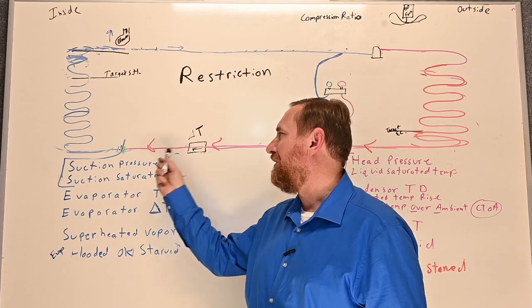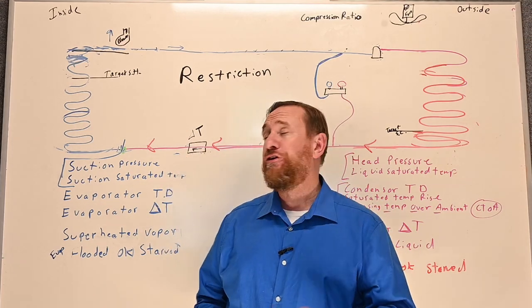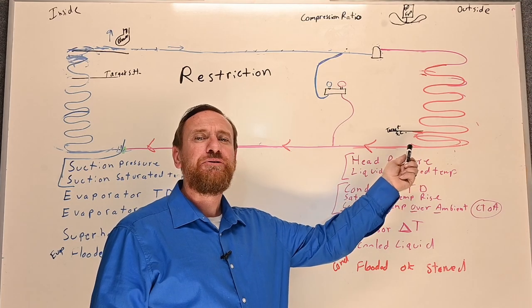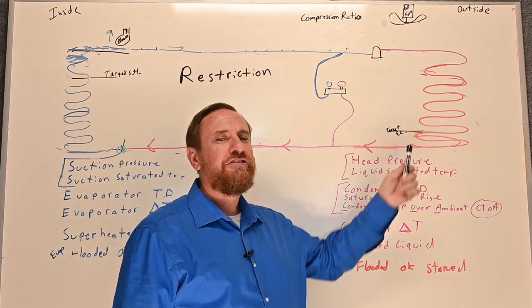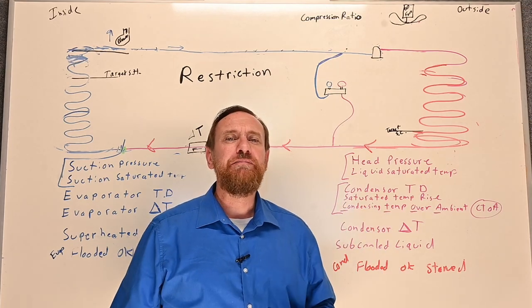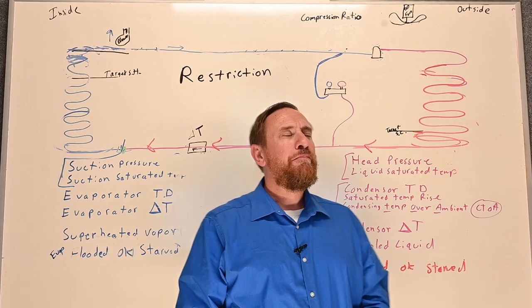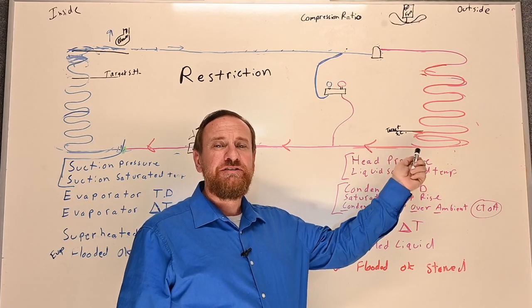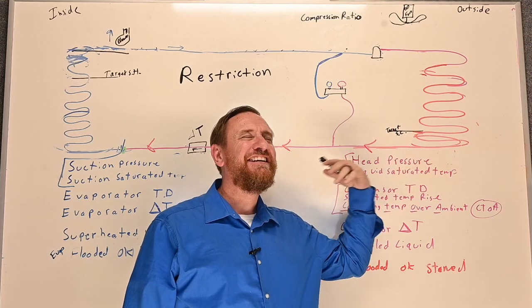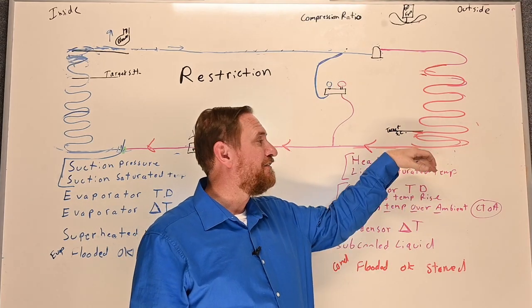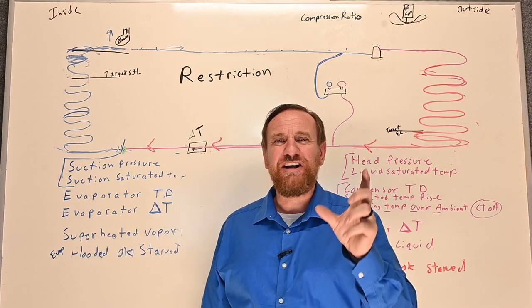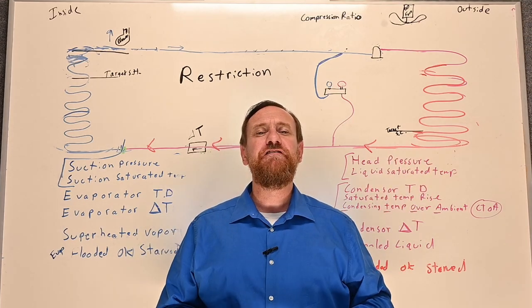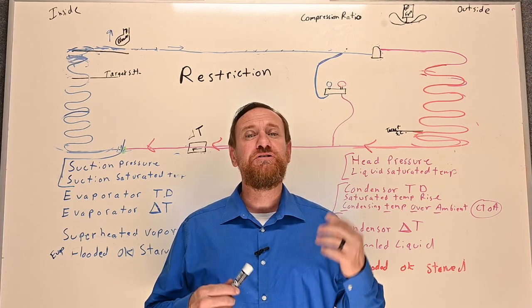All of these are possibilities. The first one to eliminate is the filter dryer — it's the easiest. Remember, the filter dryer can be located anywhere in the liquid line, ideally before the metering device, but many manufacturers now put them inside the outdoor unit. A common mistake is when someone works on a system and installs a new filter dryer outside but never replaces the existing one inside the outdoor unit. That inside filter dryer gets clogged and causes a restriction, and because it's behind the service valve you never see it. Look inside the outdoor unit — if something on the liquid line has no wires, it's most likely a filter dryer.